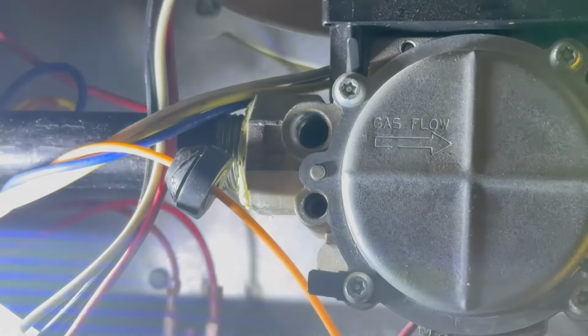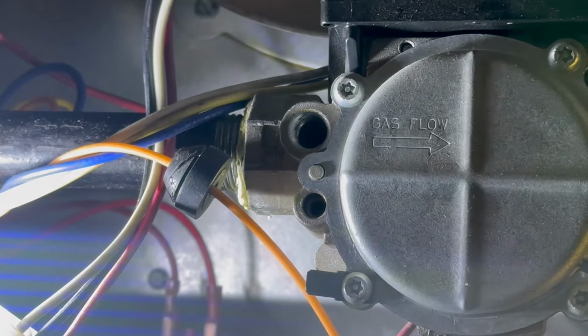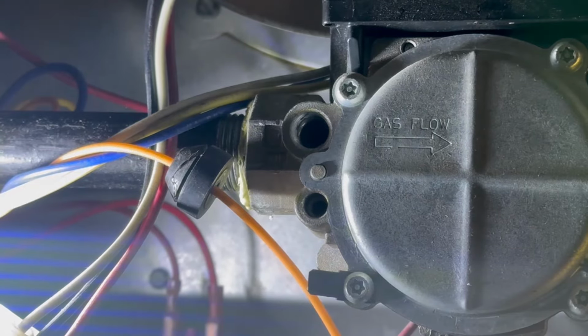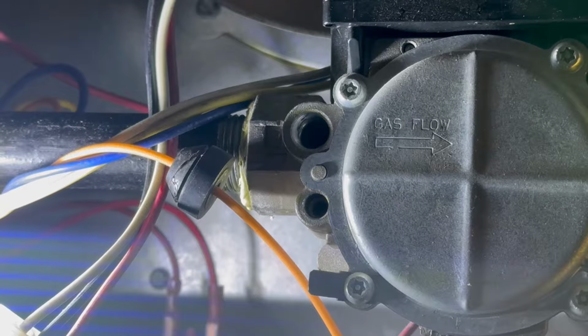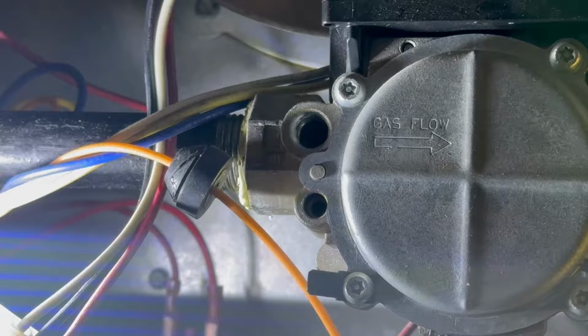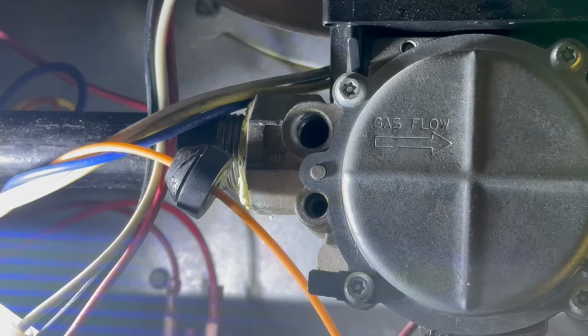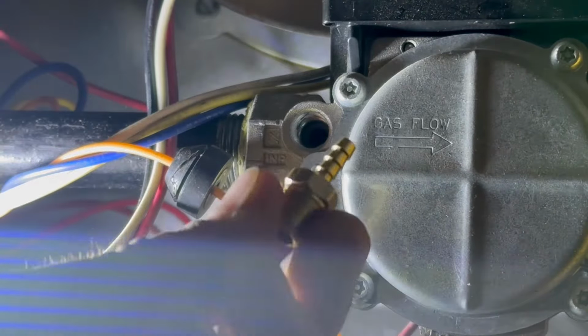Okay. So take that out. All right, it's out. So of course, if I were to open the gas valve right now, look at the gas coming out. You see that? Gas is seeping out. So you gotta put this fitting here now. So that's why I always make sure the gas valve is off first. So righty tighty. Make sure that's pretty tight.